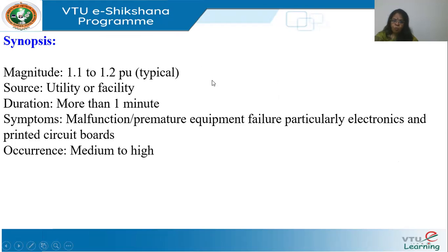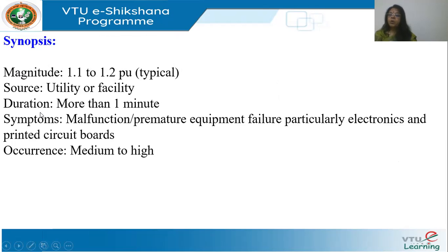Synopsis of over voltages: the magnitude is typically between 1.1 to 1.2 per unit. The source can be the utility or the facility. Duration is more than one minute. Symptoms include failure of equipment and malfunctioning. Occurrence is medium to high — they occur quite often in the system.